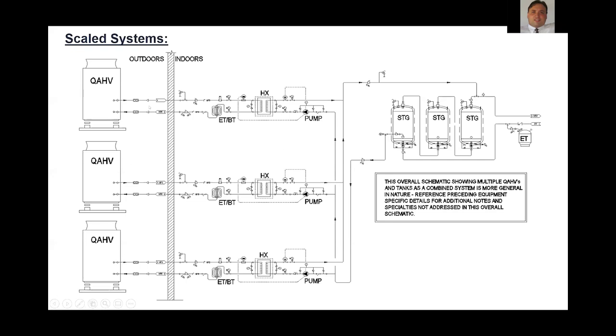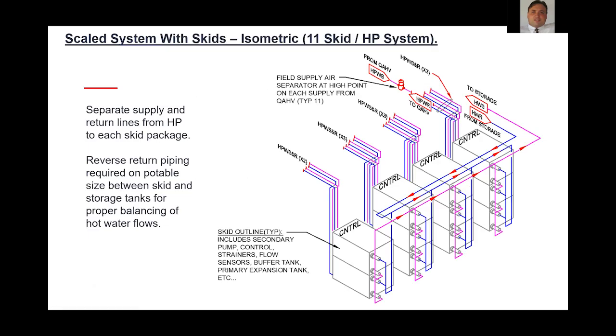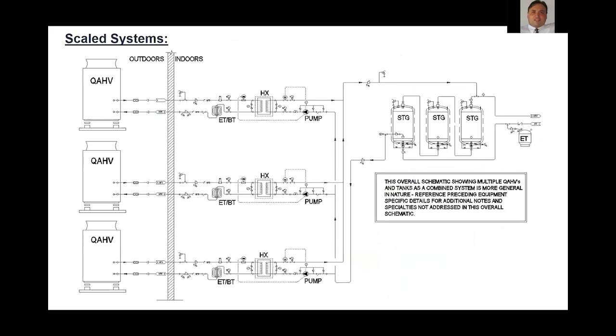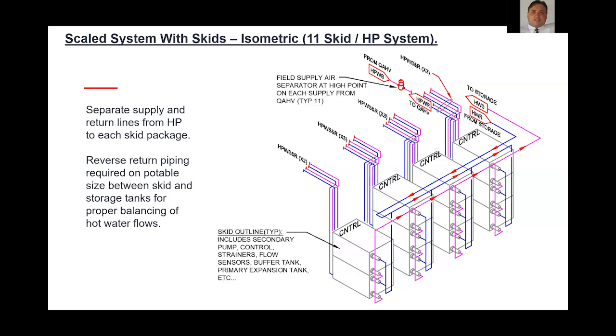So you've got dedicated water connections to each of those heat exchangers, and then reverse return piping basically between your storage tank farm and each of those secondary heat exchangers. So again, with the skid solution, this simplifies things drastically, and really takes the thought and the process of all that field work out of the equation for the installer, and really eases the burden for that installation team.